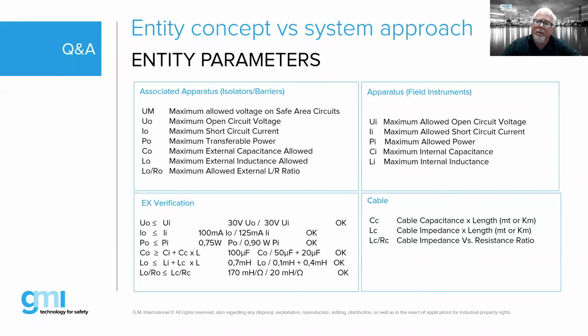The what now? Cabling, cables. Cable takes an important part in this. When we had our seminar on the 6 common mistakes, that's one of the biggest things when I go out and I'm doing an inspection on Ex intrinsic safety. I want to know the cable parameters, and I want to know the length of the cable, because cable will store energy. Obviously, the longer the length of cable, the greater the capacitance, right?